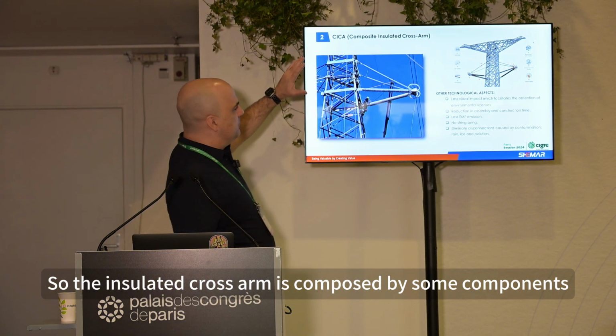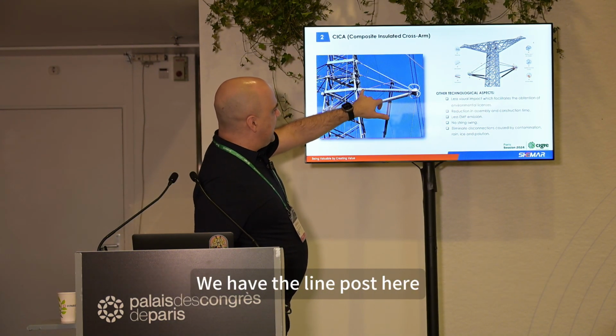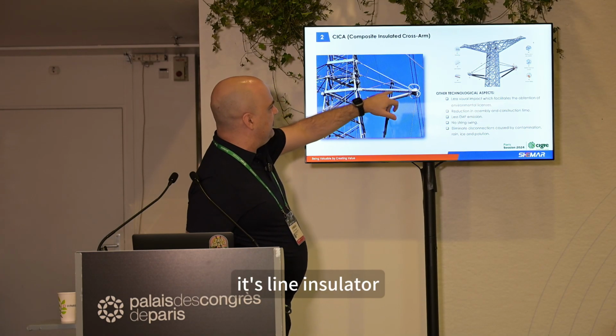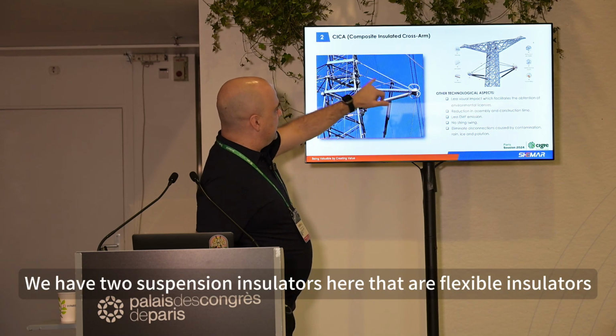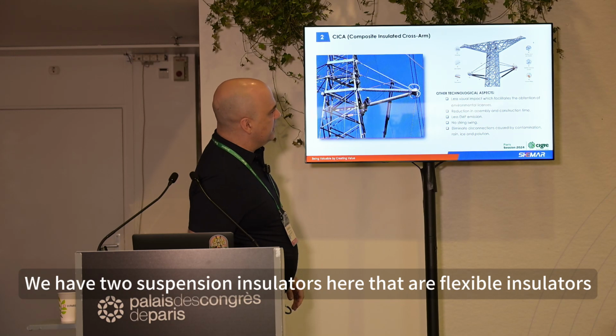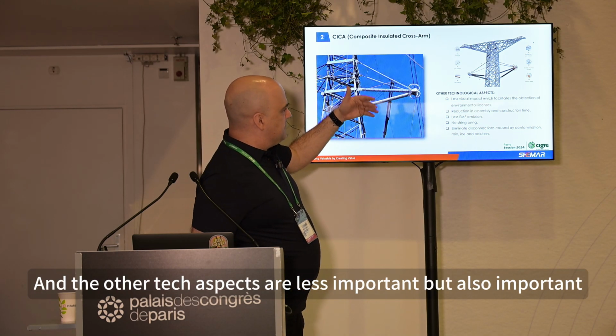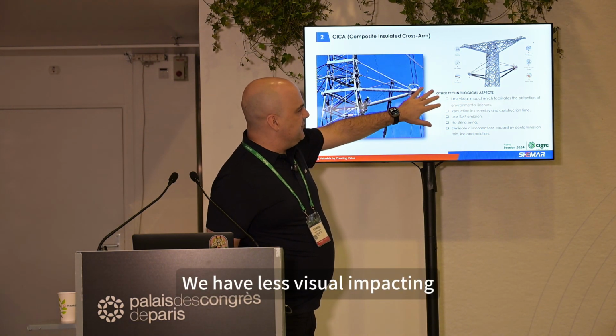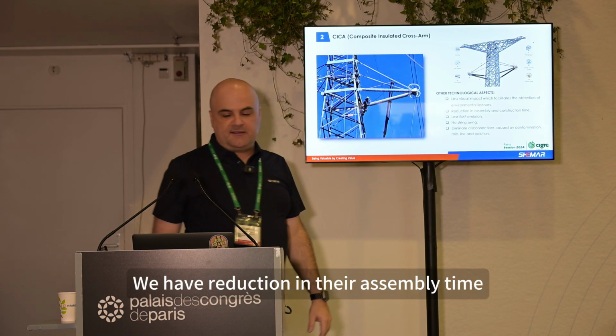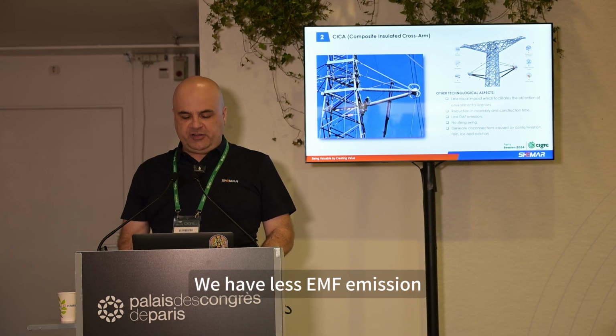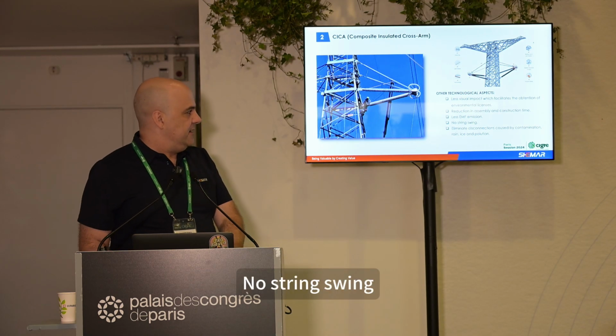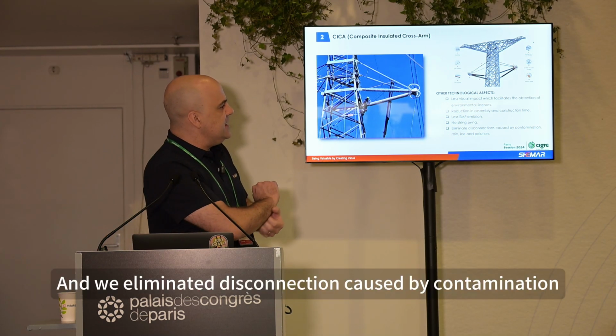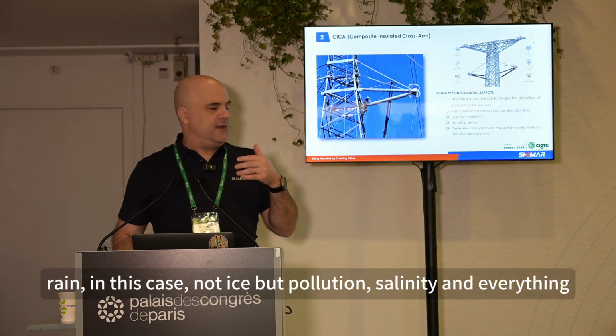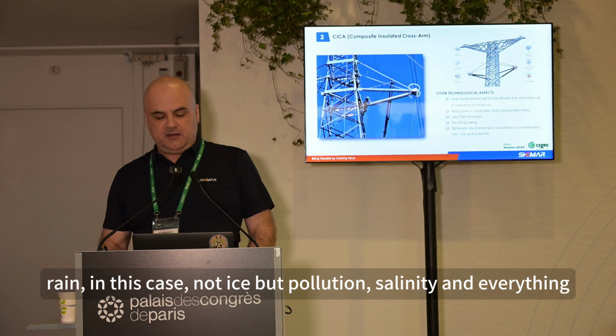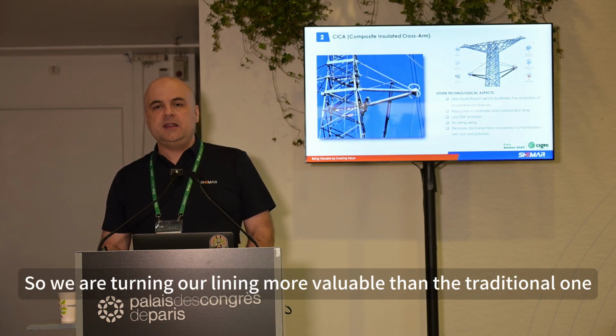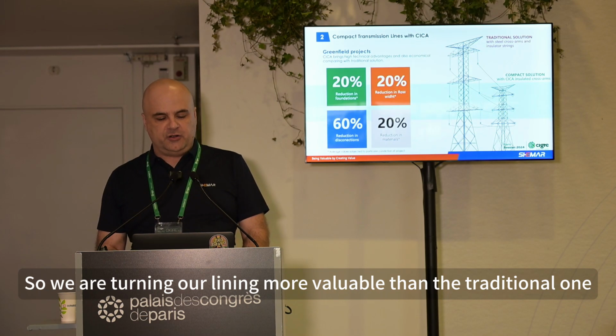The insulated cross-arm is composed of some components: we have the line posts, a rigid insulator, and two suspension insulators that are flexible insulators. Other technical aspects, less important but still relevant: less visual impact, reduction in assembly time, less EMF emission, no insulator string swing, and we eliminate disconnections caused by contamination, rain, pollution, salinity, and so on. So we are turning our line more reliable than the traditional one.